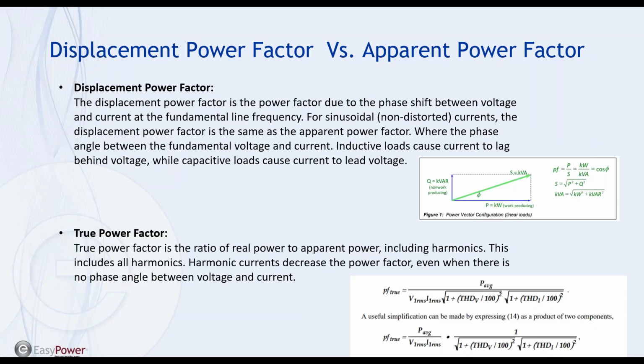And in the past 25 years, again, I have not had to enter into what is called true power factor, and I show that down here. True power factor is related to the power factor associated with the 50 and 60 hertz values, the fundamental current or fundamental voltage, but it also includes the effects of harmonics. So with an increase in harmonic currents, there will be a decrease in power factor. You are drawing more of what I would call unuseful power from the network, and that unuseful power is going to come out as a poorer power factor.